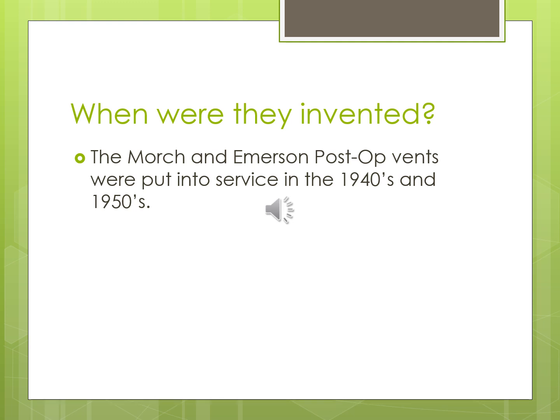The first generations of ICU ventilators came out in the 1940s and 50s — a lot later than we might guess. That Morch ventilator was a single circuit, simple piston ventilator with no monitors, no alarms, and no specific settings. Safety was essentially the eyes of the provider. The Emerson was a post-surgical vent, and those early vents didn't have trigger capabilities.